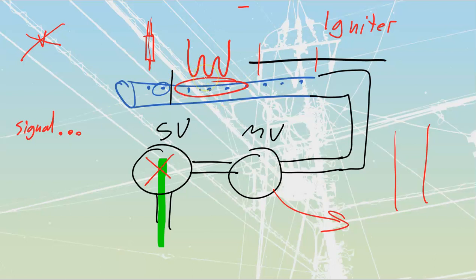Some of my DSI, direct spark ignition, probes actually incorporate the flame-proving device into them. Hot surface igniters never have the flame-proving device inside of them. Those are always going to be separate, but sometimes you will see them where the flame-proving and the spark are part of the same thing. All right, that is it for our maintenance of these.